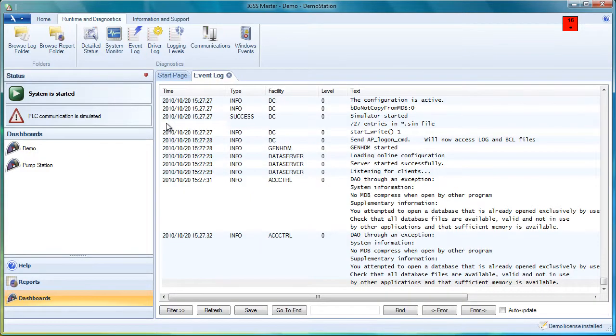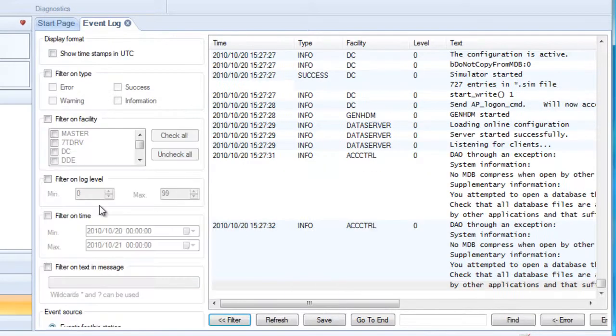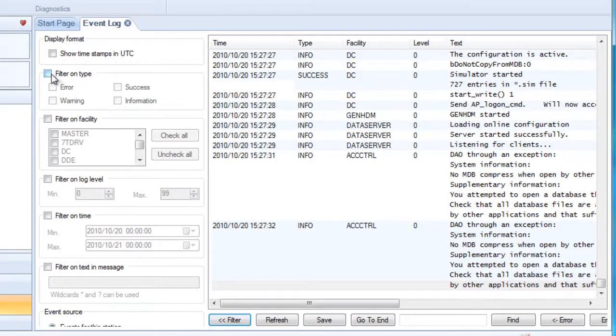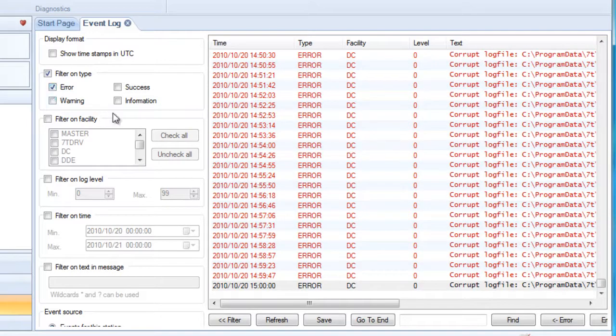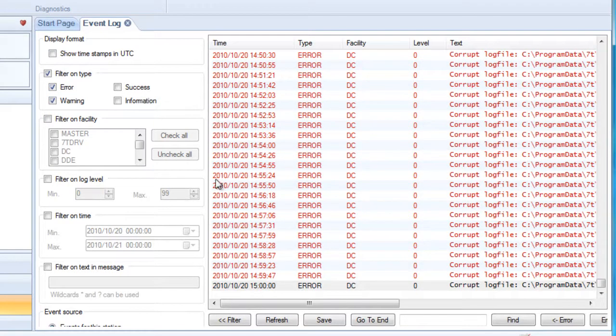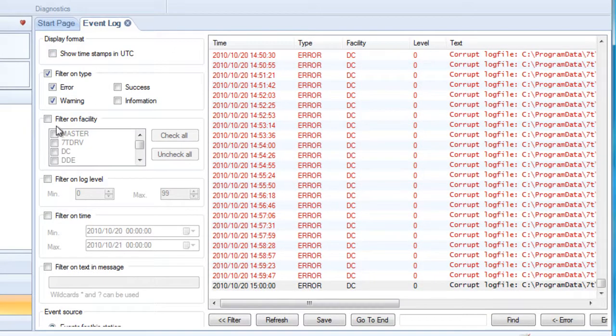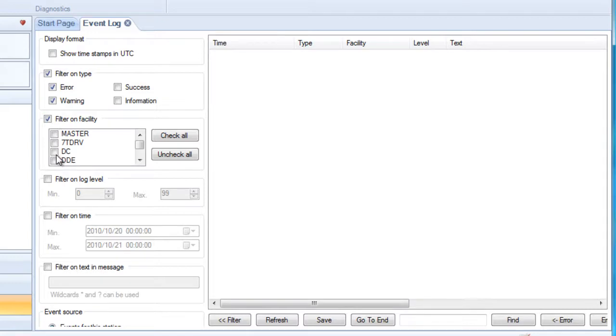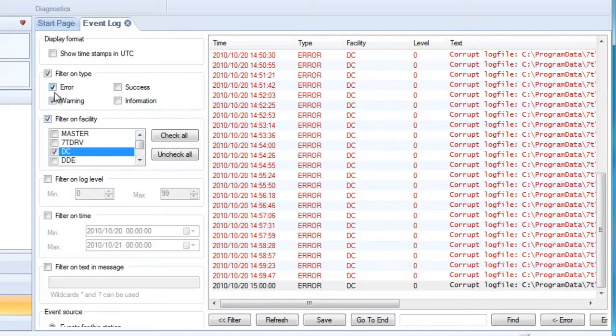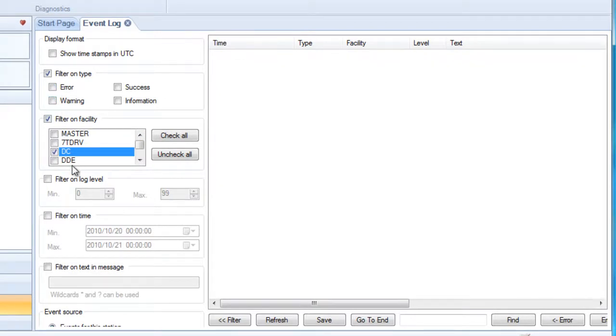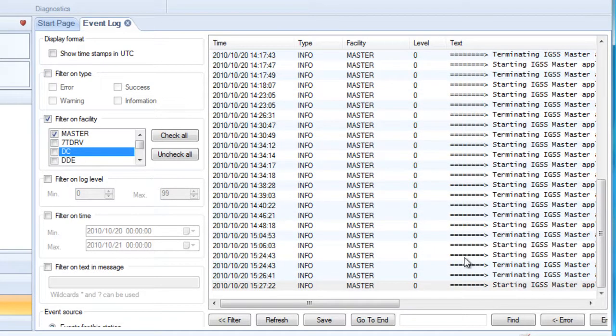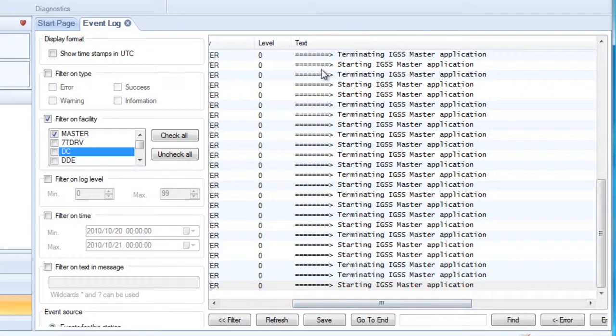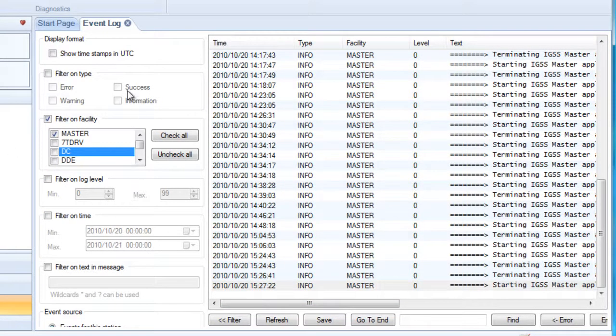Go into the event log and we see all the different events that have been written in the system. If we click on the filter button, it becomes much more intuitive, because now we can actually filter. Let's take a filter on type and say we only want to look at errors and warnings. And what you can see over here is that we have a corrupt log file, for example. We can also filter on the individual facility. This was a DC module thing. So if we switched off error and warning and put on master instead, we could see a lot of different things that we had started up the IGSS master and terminated it. This was what I just did, actually. So you have lots of filtering options here on the event log.